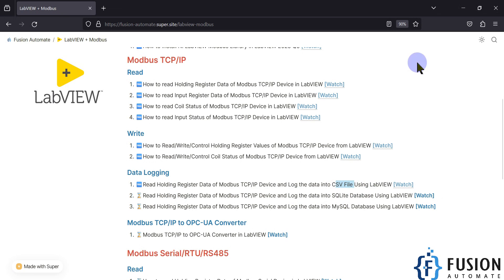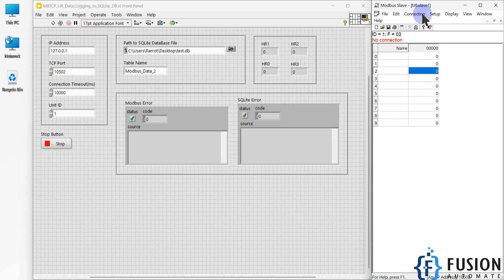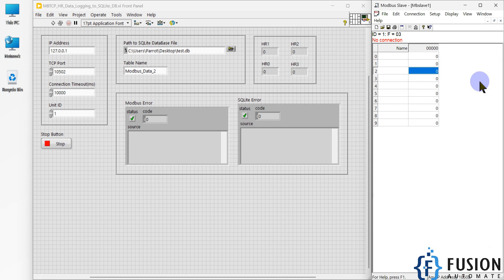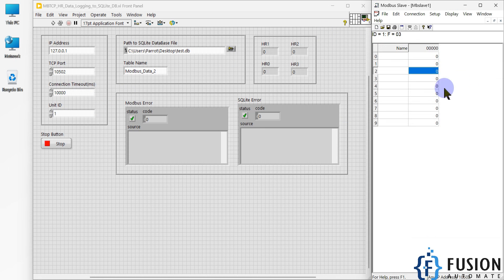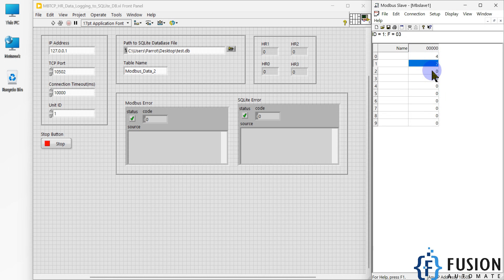Here I have created a project in LabVIEW, and here is my Modbus slave software which is acting as a Modbus TCP device. We will go to Setup, click on Slave Definition, and here you can see I have selected Holding Register because we want to log holding register data. Slave ID is one. Now we go to Connection, click Connect — the connection type is Modbus TCP/IP, so I have used the IP address and TCP port. Connection timeout is 10,000 milliseconds and the unit ID is one. My simulator is up and running, and I will simulate the holding register so its value will be incrementing automatically.